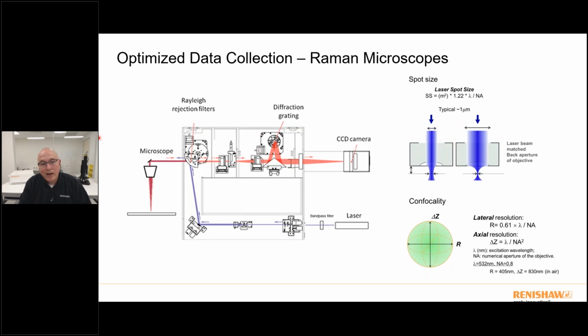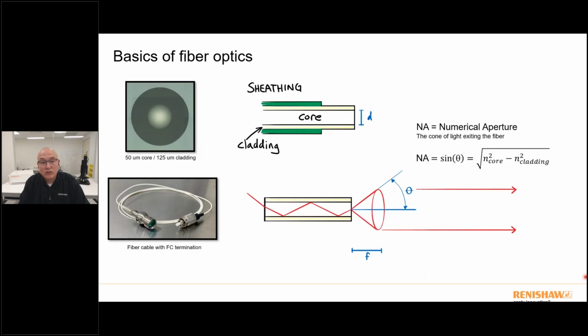So we spend a lot of time in our Raman microscope systems to make sure that we properly fill the aperture. We don't want to overfill the optic and throw photons away, and we don't want to lose numerical aperture benefits by underfilling the optic as well. And all of those go to defining lateral and axial resolution as well. So really, numerical aperture with microscope objectives is important. And that's true of a lot of applications here.